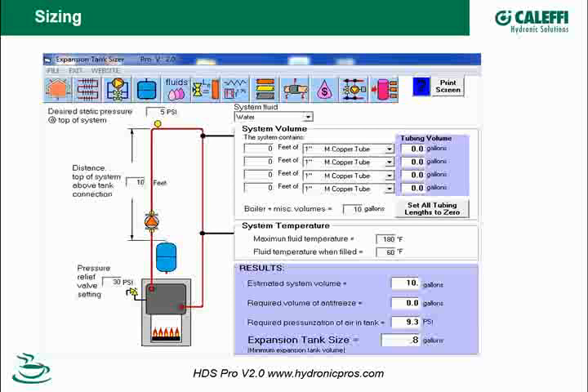Some of the tools that you can use for sizing information, we talked about sizing, making sure the equipment on the job, the boiler, the pumps, the pipes, everything on the job. This is a program that I use, a little design program from John Siegenthaler. You can look at this at hydronicpros.com. There's a little demo out there that you can play around with, but it'll do a lot of the sizing information. There's information in here for sizing pipe size, expansion tank sizing, make sure they've got the right tank installed there. If you see a pressure relief valve that's been popping off, there's a chance that the tank has been undersized, or when it was replaced, they didn't put the proper size on there.